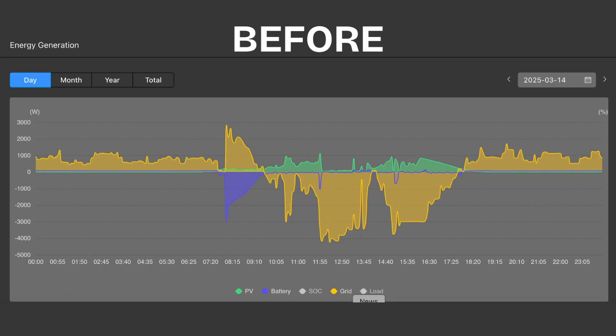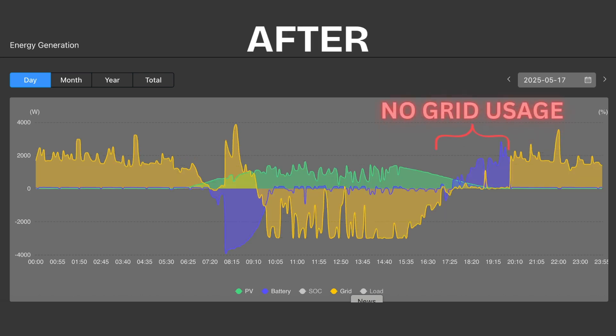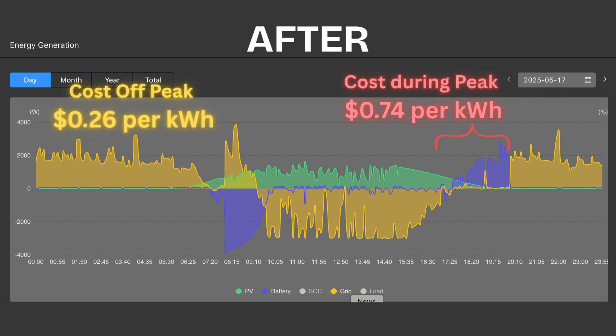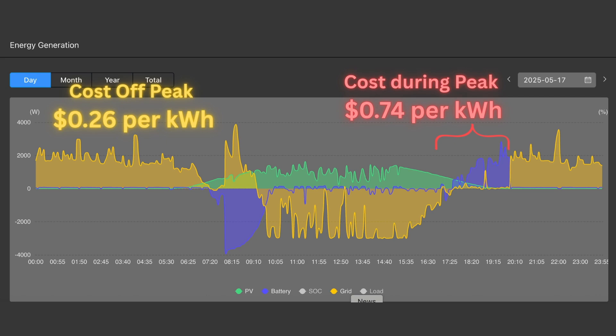Let's look at a real before-and-after example from one project. It's the same home, the same solar equipment — all I did was fine-tune the time-of-use settings. We cut peak usage down to zero: at the peak usage time, they're pulling no energy from the grid, which means they're not paying too much for electricity. Whenever they are pulling from the grid, it's usually at nighttime when energy is cheapest. Doing just this change saved them over $80 per month — that could be almost $1,000 a year — simply from reprogramming the inverter, not adding any equipment or installing anything else.